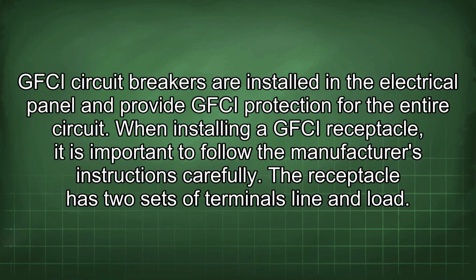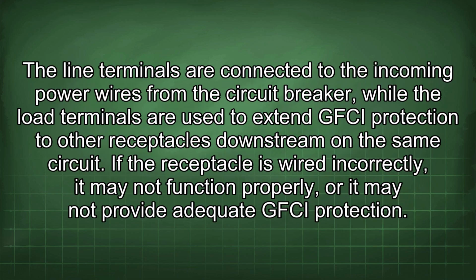When installing a GFCI receptacle, it is important to follow the manufacturer's instructions carefully. The receptacle has two sets of terminals, line and load. The line terminals are connected to the incoming power wires from the circuit breaker, while the load terminals are used to extend GFCI protection to other receptacles downstream on the same circuit. If the receptacle is wired incorrectly, it may not function properly, or it may not provide adequate GFCI protection.